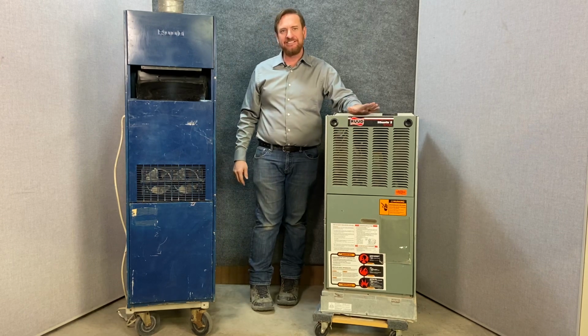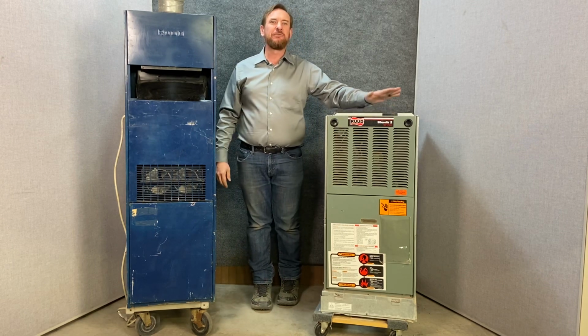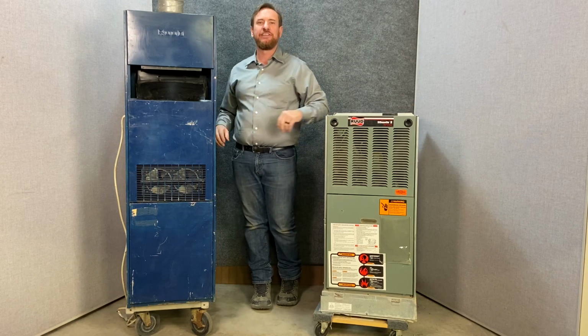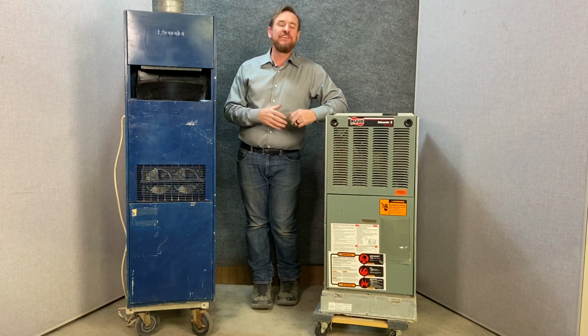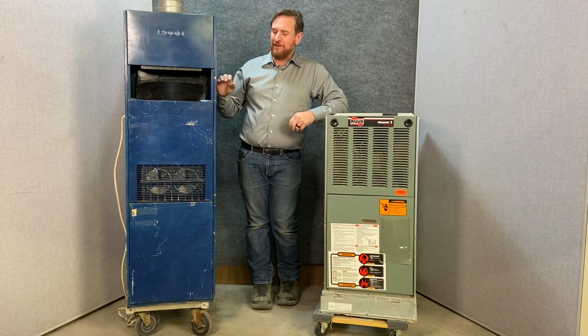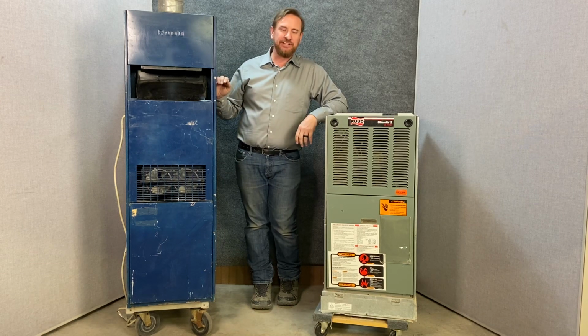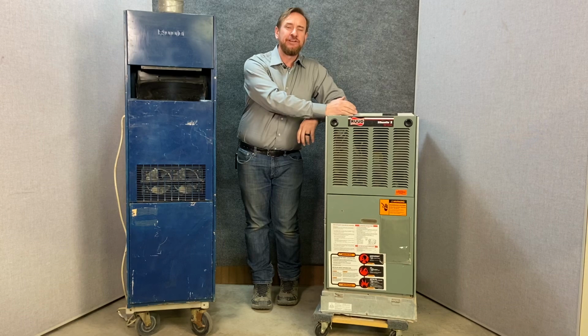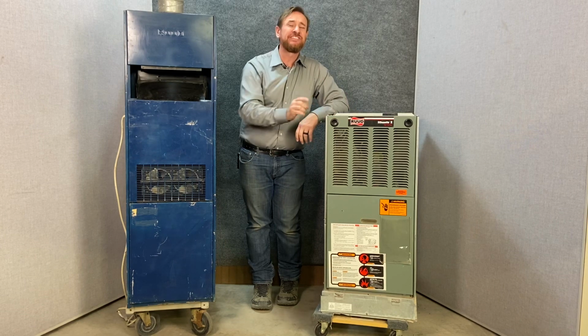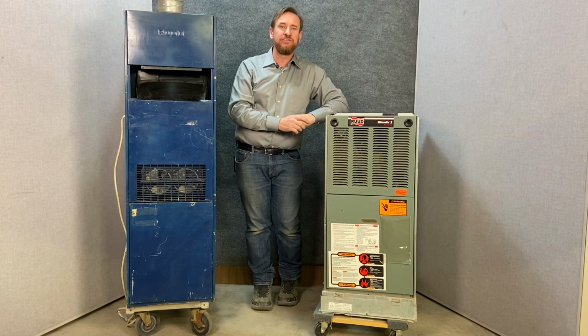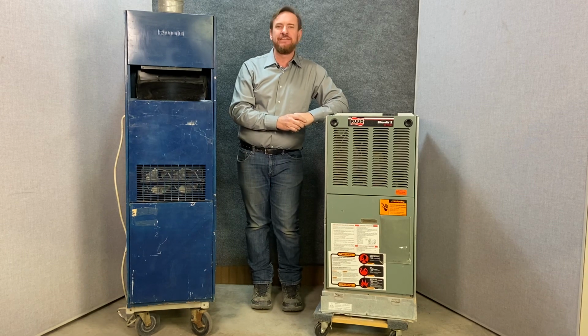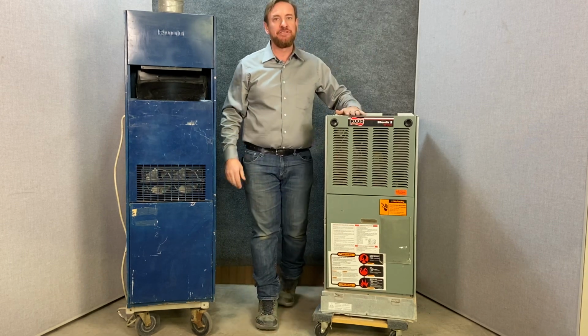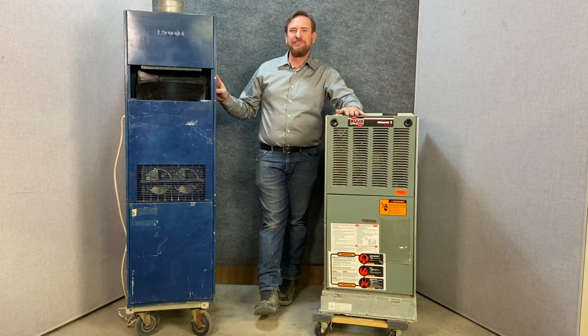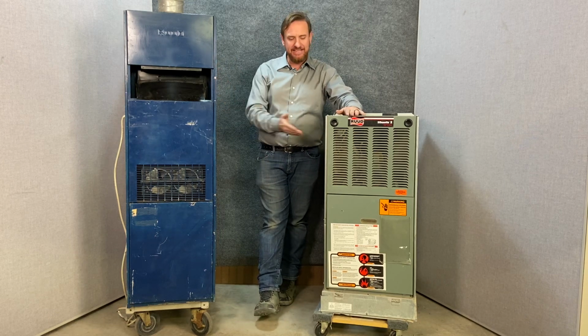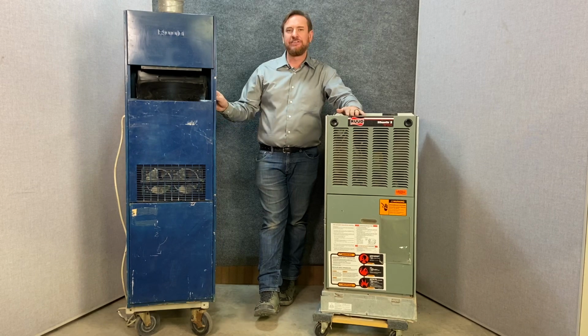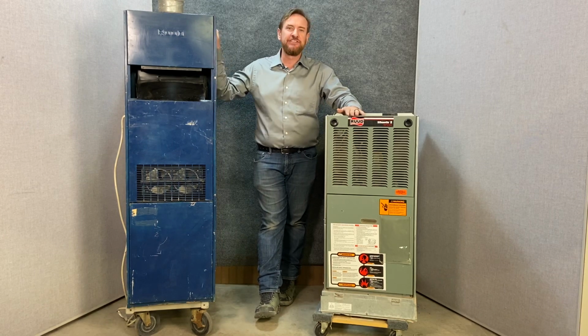This furnace right here is actually larger as far as the amount of heat we're getting into the house than this old furnace. So when you're sizing furnaces, the efficiency of that furnace is going to play a part. If I replace an 80,000 BTU furnace with a new 80,000 BTU furnace, it would be too large for the house. And oversizing a gas furnace is one of the worst things you can do. It's horrible for controlling humidity. Your customers are never going to be happy. So you've got to take into account the efficiency of that furnace when you're changing it. In this case, this 60,000 BTU furnace is going to be significantly larger than this old furnace that was there.